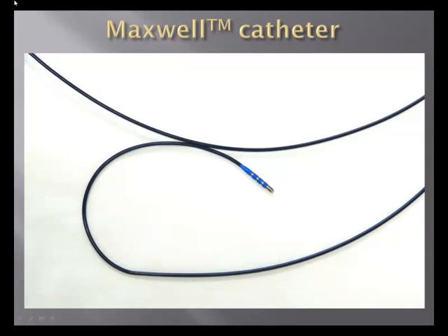Here's a close-up view of the catheter that's used. The distal pole here is also platinum metal. It is impregnated by magnets, as Josh told you, neodymium magnet particles that give us the coercivity that Josh described. And this is still the floppy section. And these interelectrode distances are clinically normal, what we use every day, so that we're not rediscovering the wheel as far as how we record or how we ablate, only how we deliver, guide the catheter.